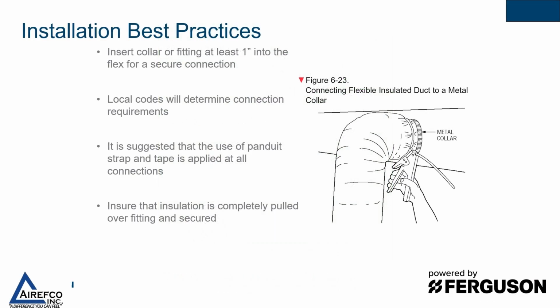When you're attaching the flex duct to a metal collar on a piece of ductwork, you need to follow local codes, of course, to determine the connection requirements. But you should insert the collar or the fitting at least 1 inch into the flex for a secure connection. It is also suggested that you use a Panduit strap and that tape is applied at all connections. Ensure that the insulation is completely pulled over the fitting and secured.